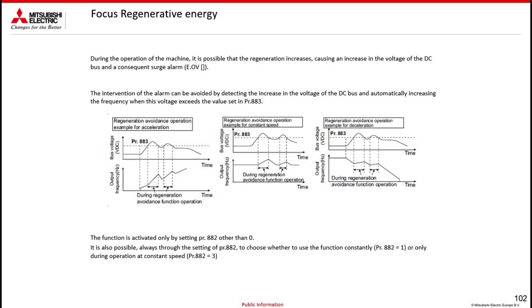But there is a but. In fact, the ramp itself is controlled because the motor never lets go, but it's not controlled over time, because you understand that this variation, where the frequency recovers, lengthens the ramp in all respects. So it's a controlled ramp, but not controlled over time. And it can also be variable, in the sense that it doesn't necessarily have a perfect cadence over time. I told it to do it in 10 seconds. It says 15, maybe it can be 14, it can be 17, it can be 12, and so on. So it's controlled but not controlled over time. Such functionality also works in acceleration, constant speed, or deceleration. Or this function can always be enabled.